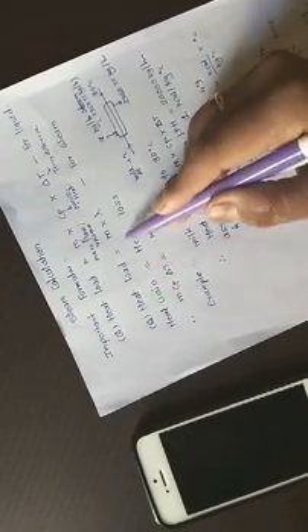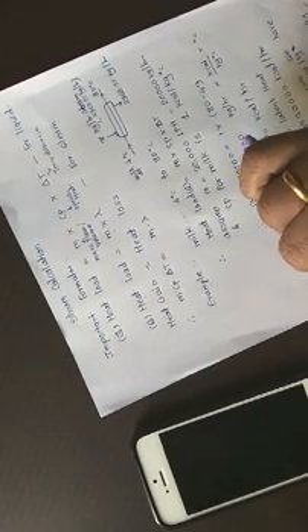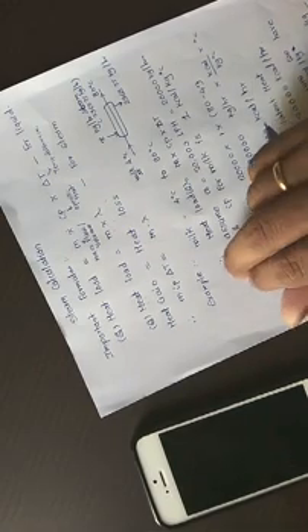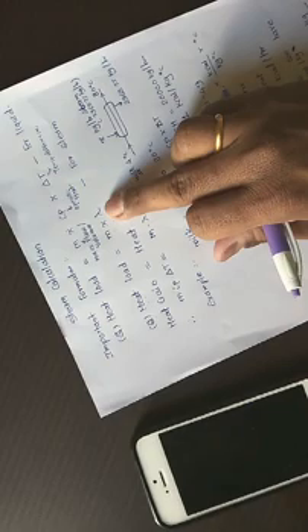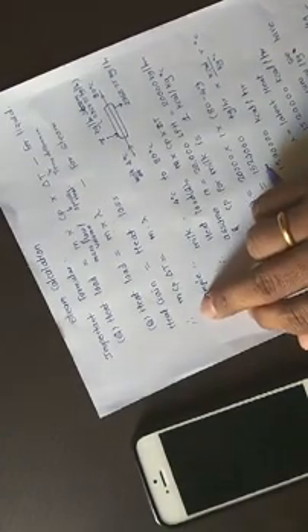For the steam side, we have the formula Q, heat load, is equal to M lambda. Why M lambda? It is for the steam. M means mass flow rate of the steam and lambda means latent heat. Latent heat we can get from the steam table. For that purpose, you should have knowledge of the steam table, or you can use Google to find lambda at what temperature or what pressure. If you search latent heat at 3 bar, you will get the value of latent heat at 3 bar from Google.